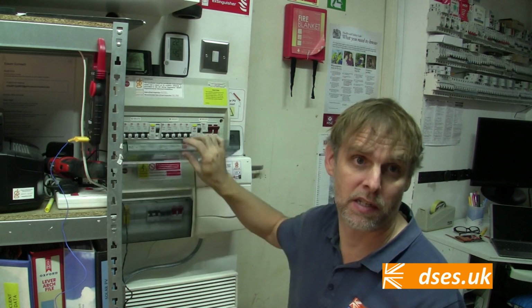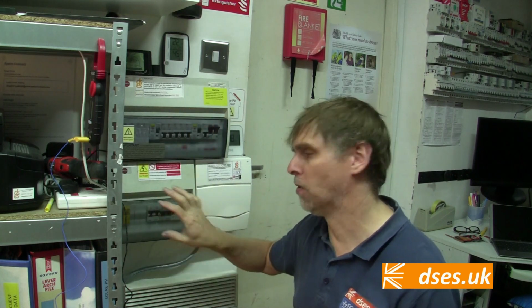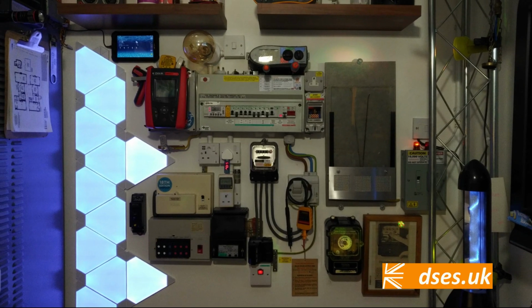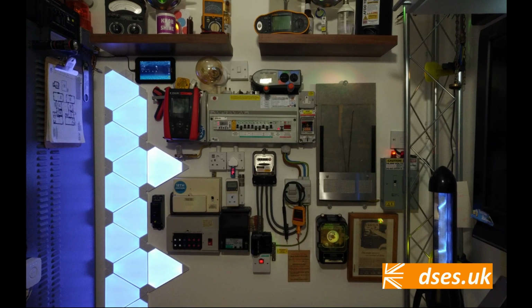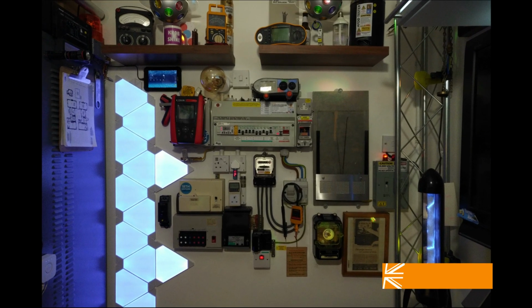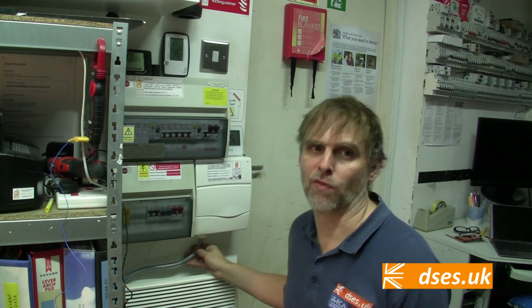A 10th circuit, a basic 40 amp breaker, will continue to supply this lower board, which will retain the surge protector and its associated MCB, plus a 16 amp breaker to supply the feed to my wall of death, as I don't want RCD protection on that at this end. If I'm demonstrating an RCD or earth fault in the cave, then I want that to happen over there. That's fine, as the supply cable to that is surface mounted, so it doesn't require RCD protection. And yes, it is SY cable, which is not approved for such use, but it's adequate for the task here.